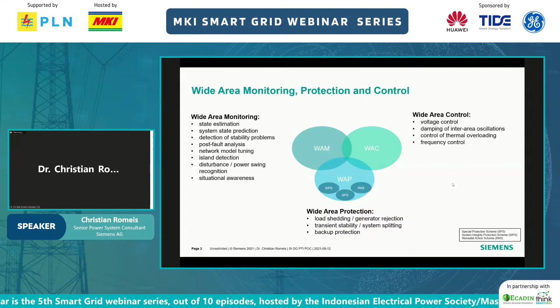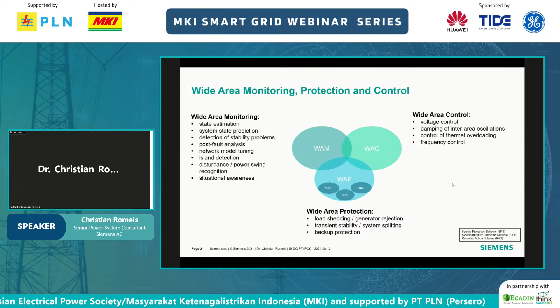On the right side is wide area control. You can introduce control schemes for voltage, frequency, and also for damping inter-area oscillations. One idea is to use PMU-based voltage differences between different areas to control the active power flow between two areas, which helps damp inter-area oscillation.